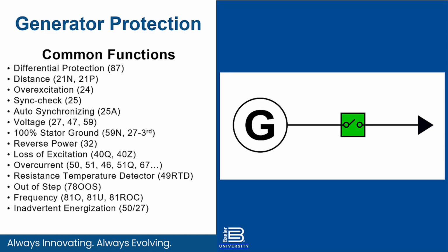From an algorithm standpoint, it's the same algorithm in the BE1-FLEX that we can apply to either a generator or a transformer, or even both if you happen to have a unit differential, but you can apply it to both or either as you wish. Some of the other functions, it can do automatic synchronizing, can do reverse power on even a single phase, so you can have a single phase reverse power condition. Loss of excitation can be either VAR based or impedance based.